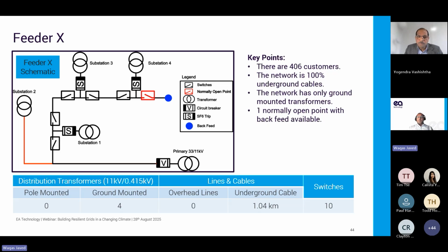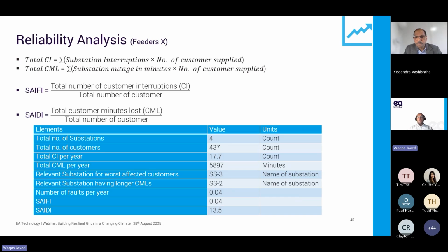The target tool runs thousands of fault scenarios on feeder X to evaluate the reliability profile under current conditions, counting customer interruptions or customer minutes lost — known as SAIFI and SAIDI in Australian terminology. The model helped identify which substations are most affected: substation 3 contributed most to customer interruptions, while substation 2 had longer restoration times and contributed disproportionately to customer minutes lost. Interestingly, the number of faults simulated per year was very low, but because of the feeder's configuration, a single failure often resulted in long restoration times for a large proportion of customers. This reinforces that resilience isn't just about fault rates — it's about response and recovery as well.